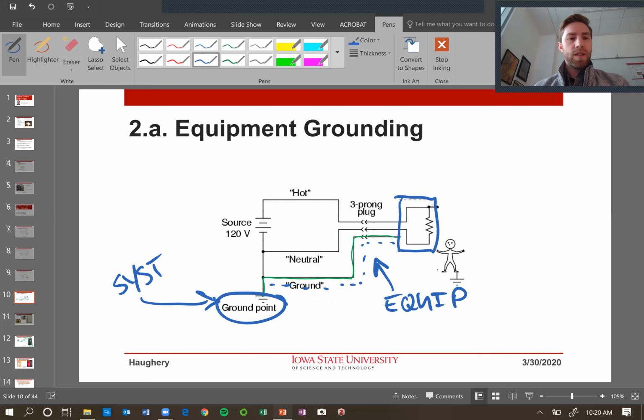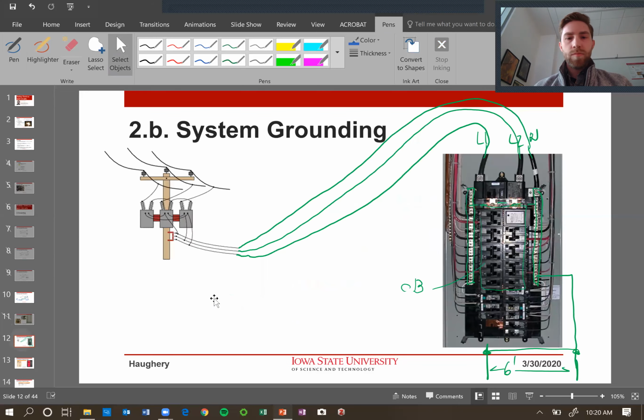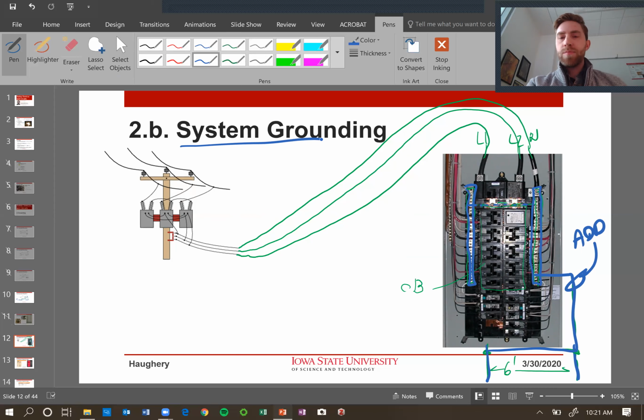And we can show that on this page here, where we actually take a ground bar, actually two ground bars, and we connect them to our ground bus terminal point in our electrical enclosures. And the two sides of this panel have two ground buses. They are going to be internally connected so that they're both grounded. And once we add this connection here, we've now made that system grounding point, okay, because we've grounded the main power distribution panel, that main grounding point in the system, to ground. A little difference between equipment grounding versus system grounding.